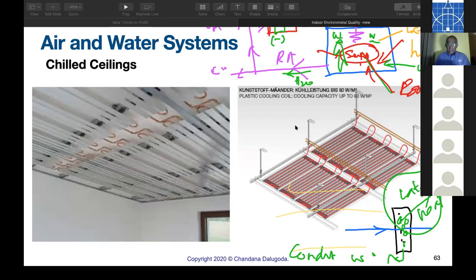Latent heat is in the coil. That you've got to remember very carefully. In an air conditioned room, you have only the sensible heat. There's no latent heat. There's only water vapor. Water vapor has to go back to the cooling coil. The moment it condenses, latent heat gives off.